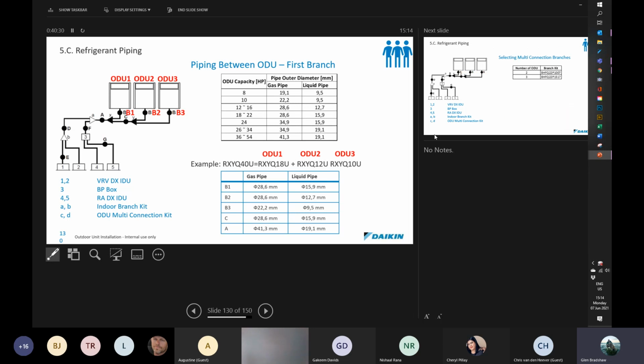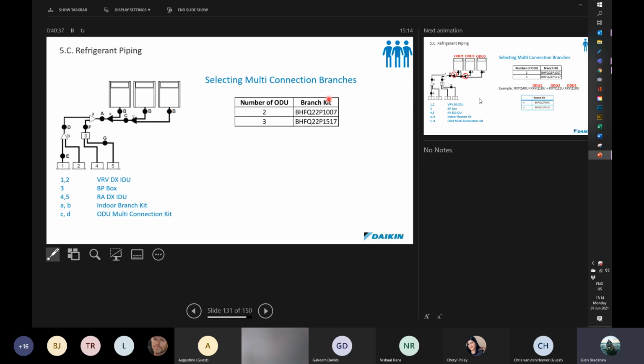Okay, and then obviously when you've got multi-condensers, outdoor 1, 2, and 3. Okay, and if we go on, then also looking at the different branch kits that might be required, making sure that when you pick up a branch kit out of the container or wherever you're storing your products, that you pick up the right ones that you need for a particular condenser set. Look at your schematic and make sure that you're selecting the right ones and that you don't get up there and then because it's a long way back, you're tempted to try and make a plan, which is not going to be very good for the unit.